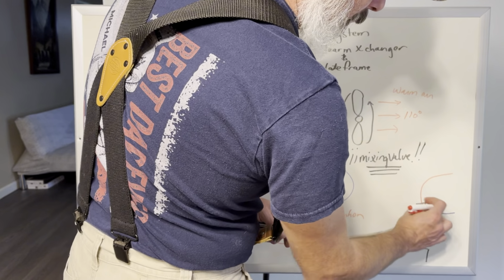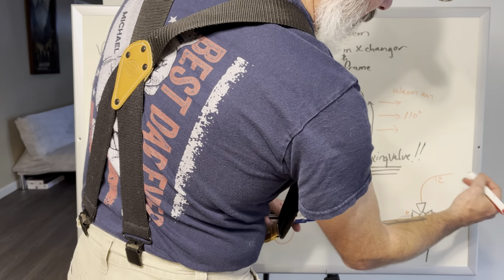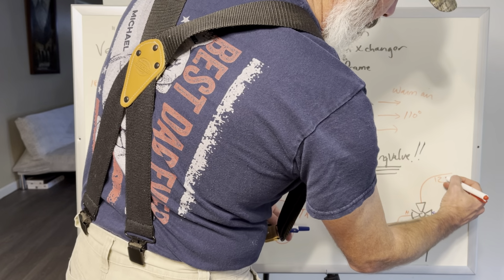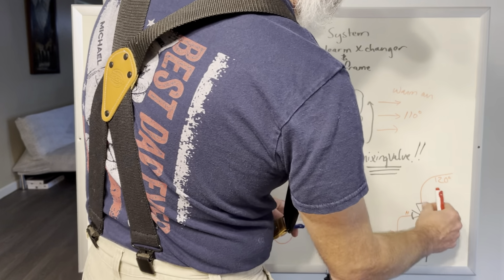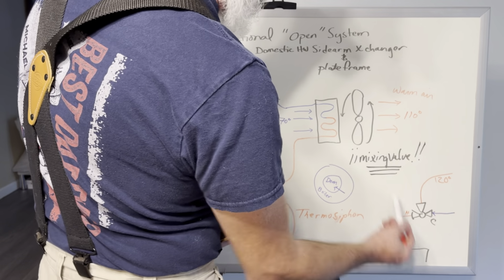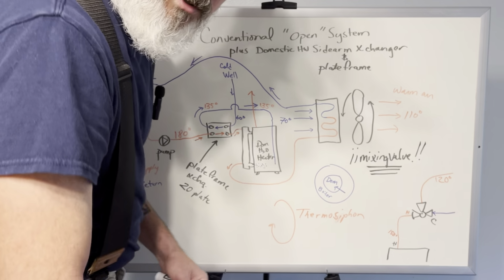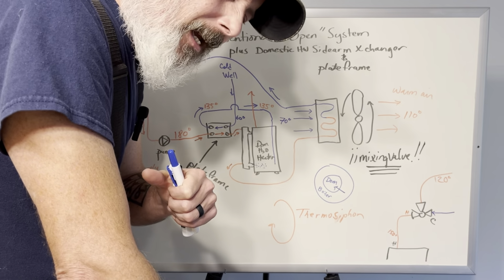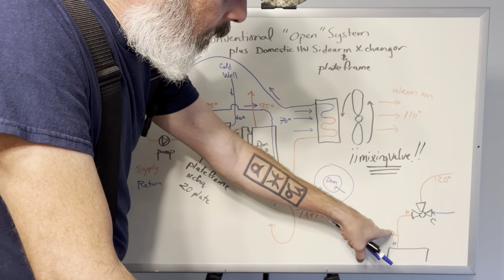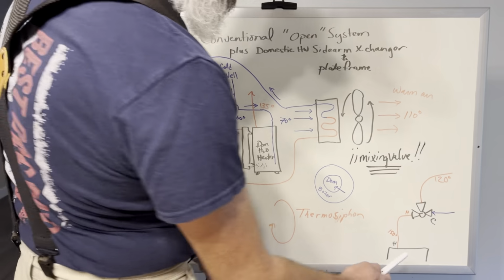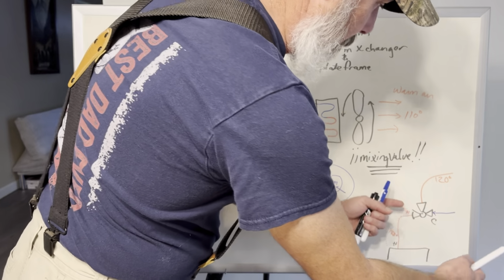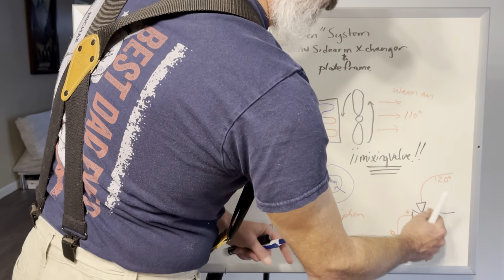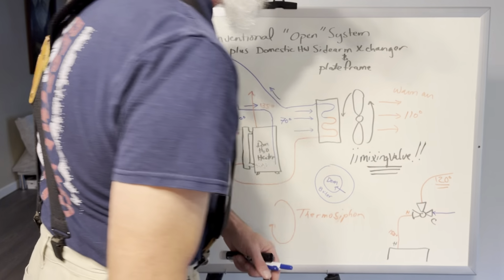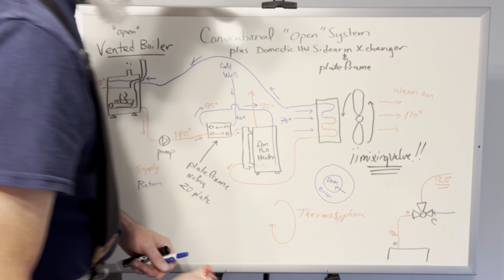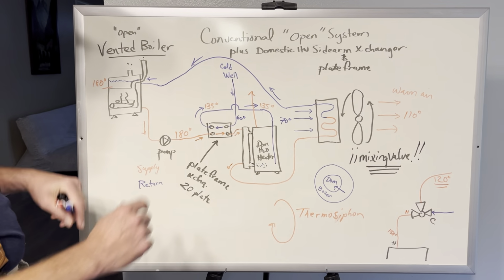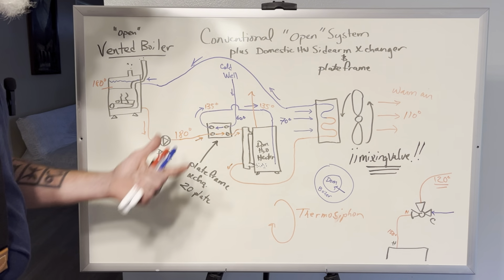Your mixing valve is adjustable to control your temperature, something modest and safe. 125 is kind of high, but let's say you adjust this to 120. So no matter how hot the water is coming out of this tank, and it will get hot, if this is set up right, a good install, man, it will scream, and you're gonna love it. That water will be devastatingly hot. But no matter how hot this water is, the valve will either back off and close off the hot. It'll just be constantly blending and tempering to a controlled temperature. Very important. Mixing valve.